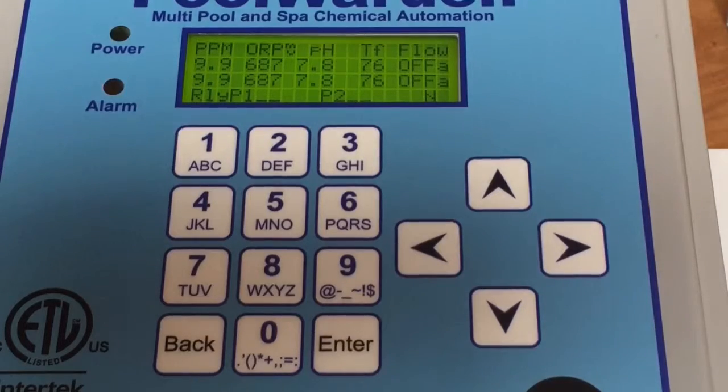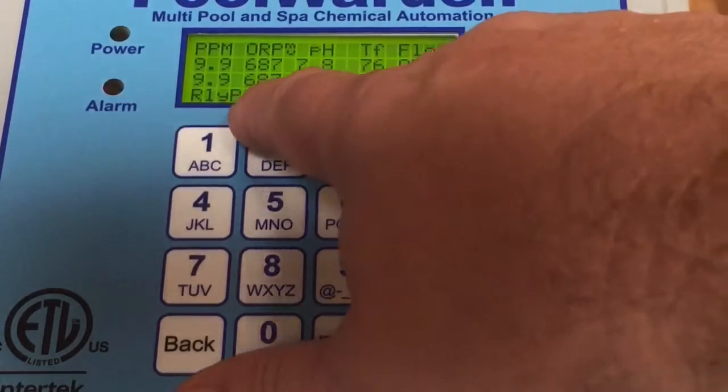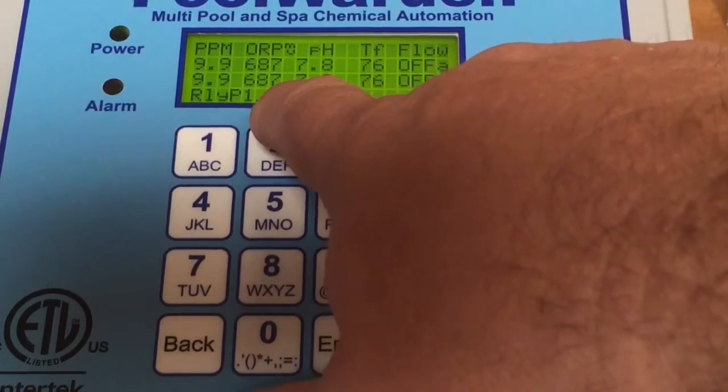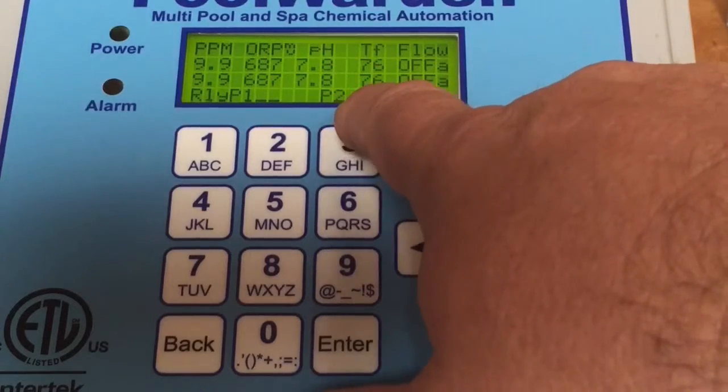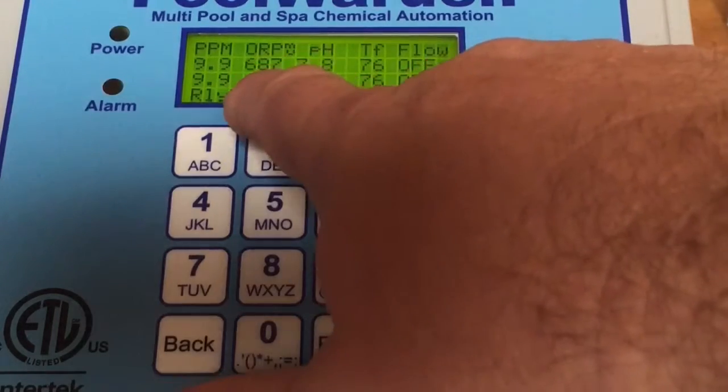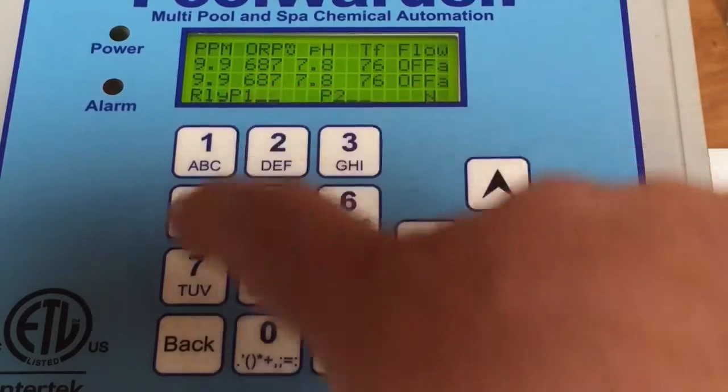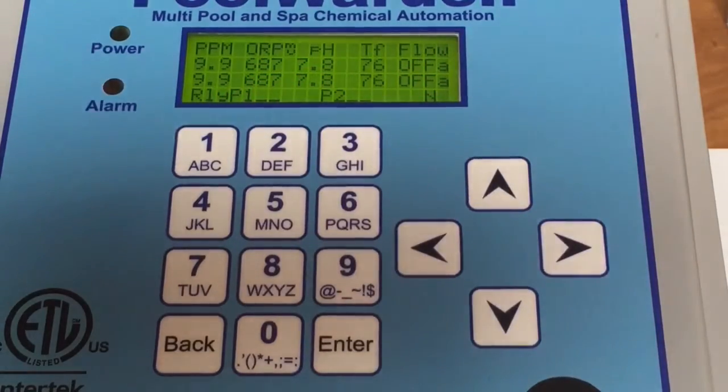Also, if you see an O in any one of these spots—this would be your ORP, this would be your pH on pool one, and ORP and pH on pool two—if there's an O here instead of the line or the arrows, that means it has gone into overfeed and it will not function anymore until that overfeed is reset.